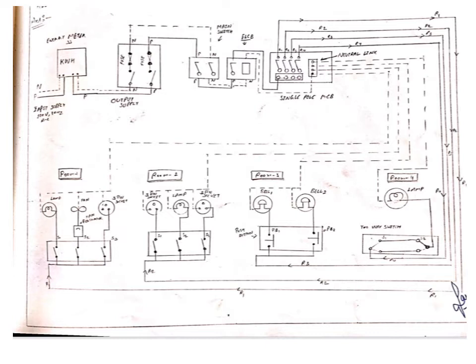On subcircuit 1, for example, you can see here on the left hand side, it is one lamp, one fan, and one 3-pin socket. So we have connected three switches. The phase we have taken from the distribution board, we have given to all three switches. From one switch the phase will go to the lamp, and from another switch the phase will go to the fan regulator, because the fan regulator is connected in series with the switch.